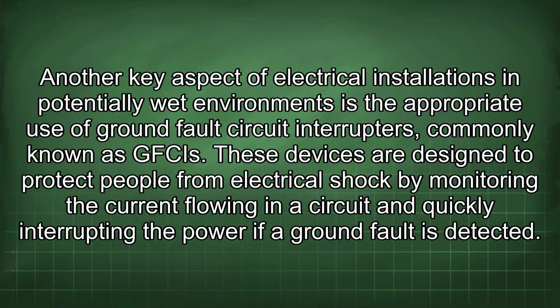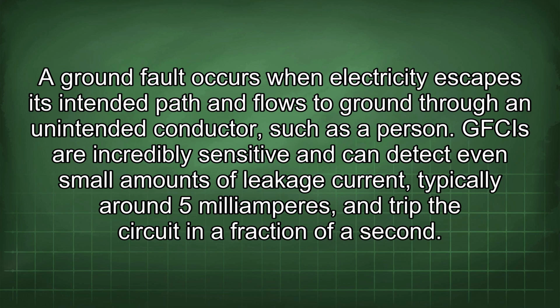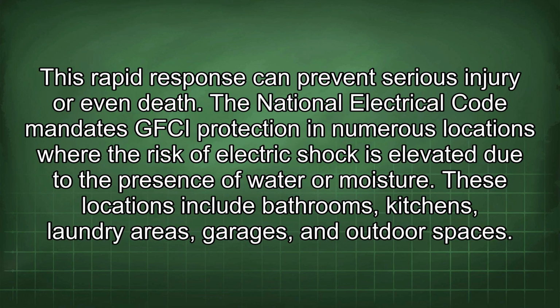Another key aspect of electrical installations in potentially wet environments is the appropriate use of ground fault circuit interrupters, commonly known as GFCIs. These devices are designed to protect people from electrical shock by monitoring the current flowing in a circuit and quickly interrupting the power if a ground fault is detected. A ground fault occurs when electricity escapes its intended path and flows to ground through an unintended conductor, such as a person. GFCIs are incredibly sensitive and can detect even small amounts of leakage current, typically around 5 milliamperes, and trip the circuit in a fraction of a second. This rapid response can prevent serious injury or even death.